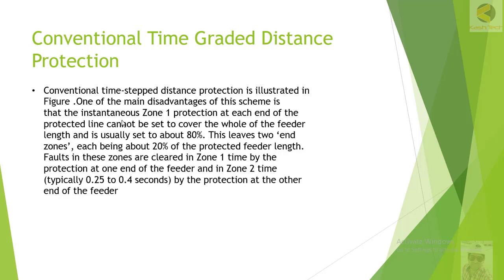One of the main disadvantages of the scheme is that the instantaneous Zone 1 protection at each end of the protected line cannot be set to cover the whole feeder length, and is usually set to 80%. This leaves two end zones, each being about 20% of the feeder. Faults in these zones are cleared in Zone 1 time by the protection at one end of the feeder, and in Zone 2 — typically 0.25 to 0.4 seconds — by the protection at the other end.